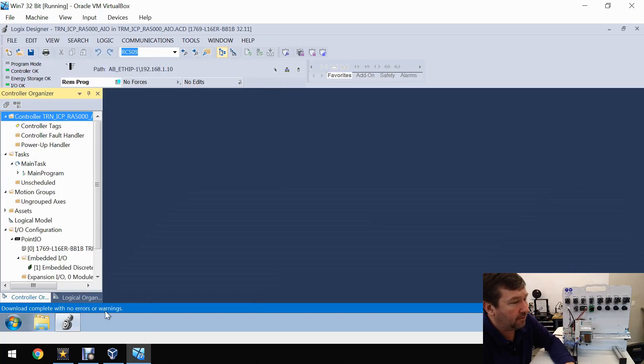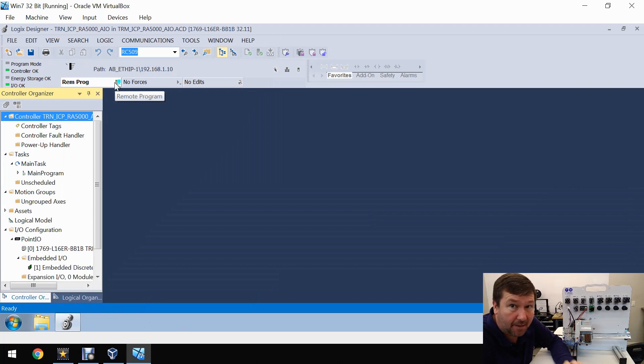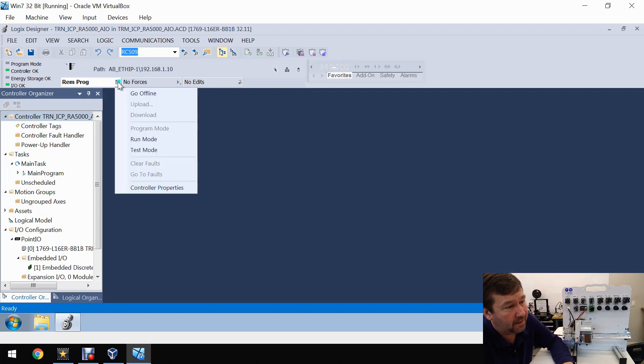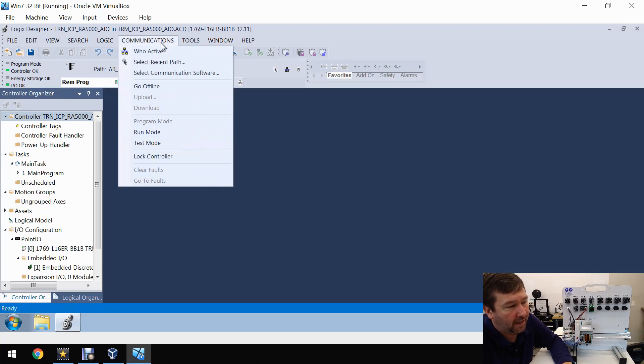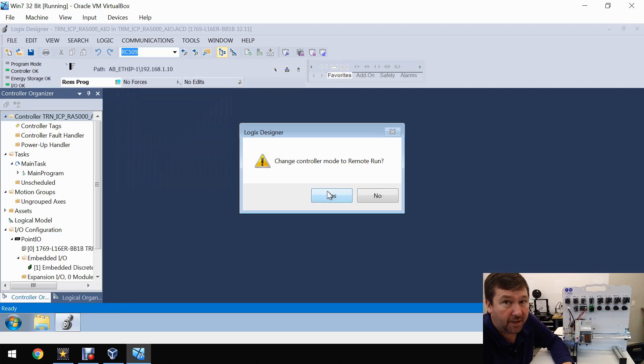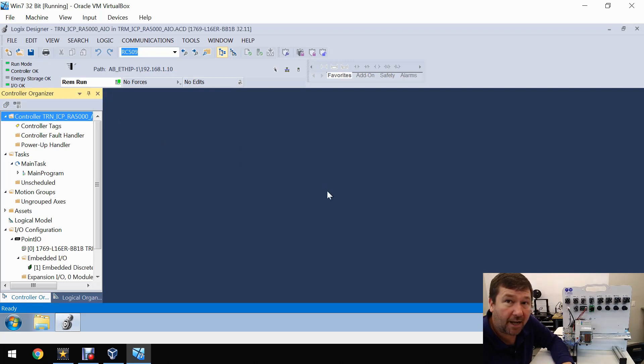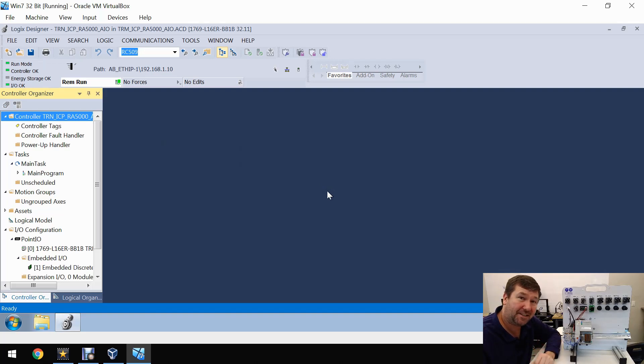Download complete with no errors or warnings. One final step to get your PLC in operation is to switch it to remote run mode. You can do that by the controller status prompt right here, switch to run mode, or you can go up under Communications and go to run mode. It's going to verify you want to change to run mode — click Yes. We are now in run mode, and that's all there is to downloading a program to your PLC.